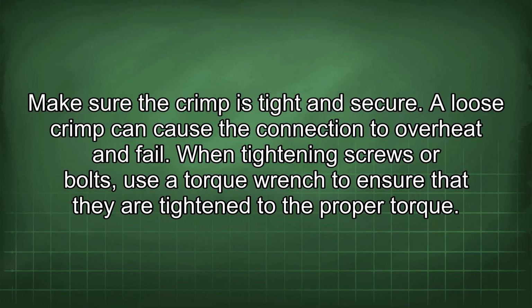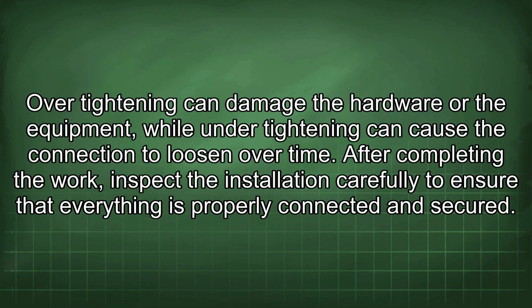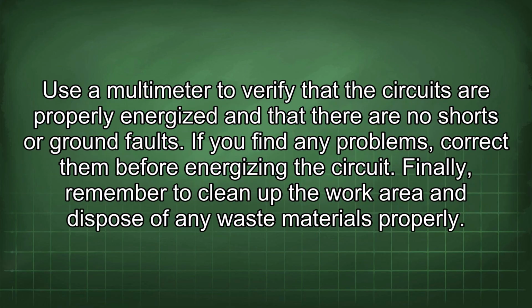When tightening screws or bolts, use a torque wrench to ensure that they are tightened to the proper torque. Over-tightening can damage the hardware or the equipment, while under-tightening can cause the connection to loosen over time. After completing the work, inspect the installation carefully to ensure that everything is properly connected and secured. Use a multimeter to verify that the circuits are properly energized and that there are no shorts or ground faults. If you find any problems, correct them before energizing the circuit.